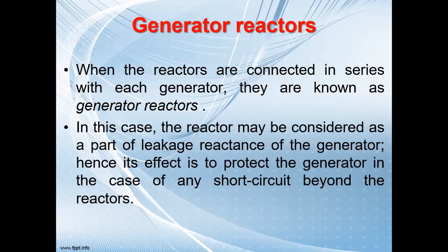When the reactors are connected in series with each generator, they are known as generator reactors. In this case, the reactor may be considered as a part of the leakage reactance of the generator. Hence, its effect is to protect the generator in the case of any short circuit beyond the reactors. So if any fault occurs beyond the reactors, it will not enter into the generator. It will limit the fault current.